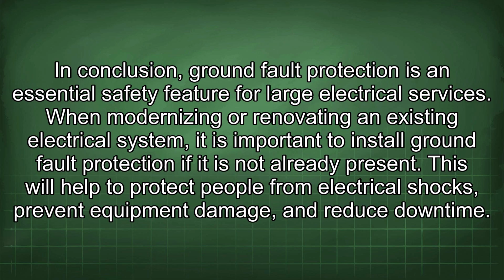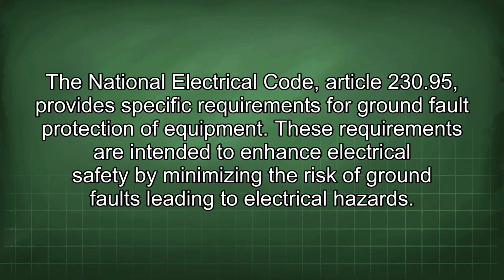In conclusion, ground fault protection is an essential safety feature for large electrical services. When modernizing or renovating an existing electrical system, it is important to install ground fault protection if it is not already present. This will help to protect people from electrical shocks, prevent equipment damage, and reduce downtime. The National Electrical Code, Article 230.95, provides specific requirements for ground fault protection of equipment. These requirements are intended to enhance electrical safety by minimizing the risk of ground faults leading to electrical hazards.